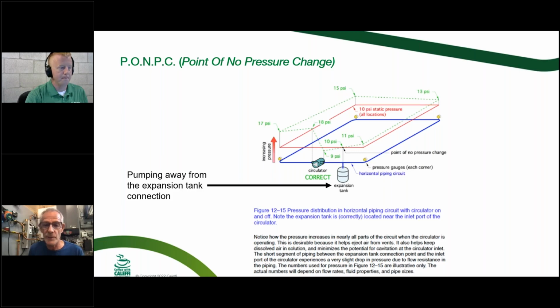Now notice there's a little bit of droop in pressure between the tank and the pump, because there's a little bit of pipe there, a little bit of pressure drop. But when you pump away from the expansion tank, all the pressure differential that little circulator can add to this loop shows up immediately as an increase in pressure. So you'll notice we filled at 10 pounds everywhere in that system at that elevation, and as soon as the pump kicked on, we went up to 18 PSI.